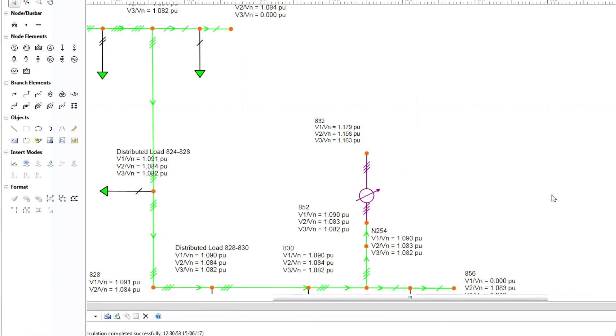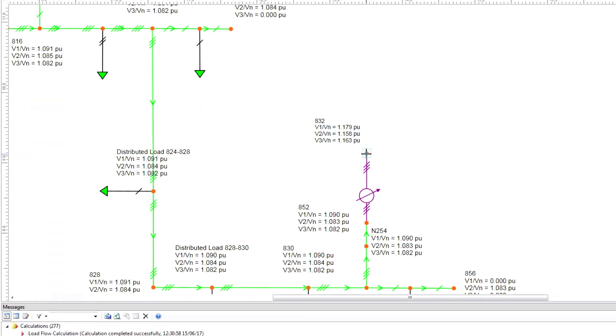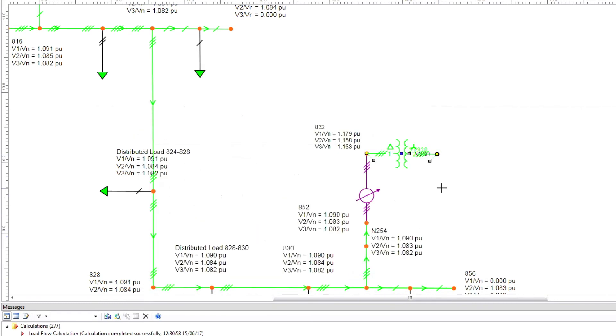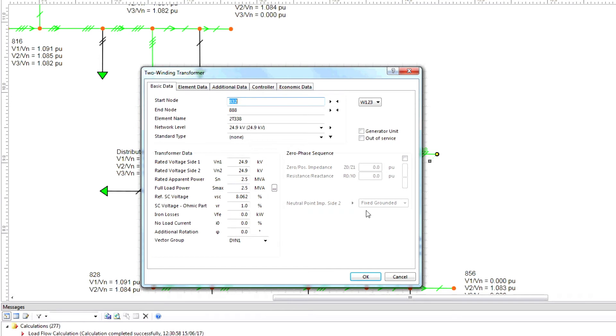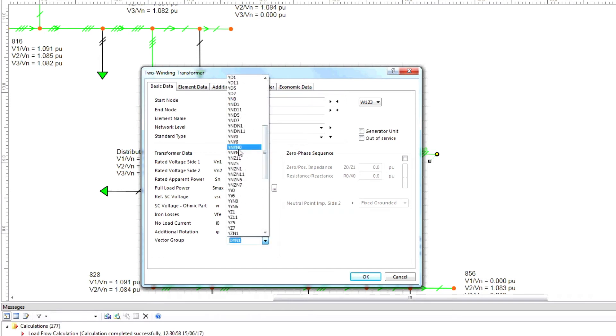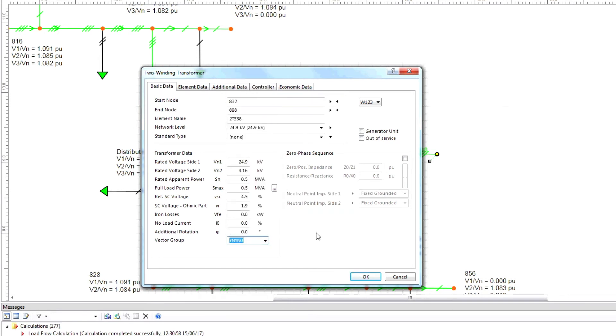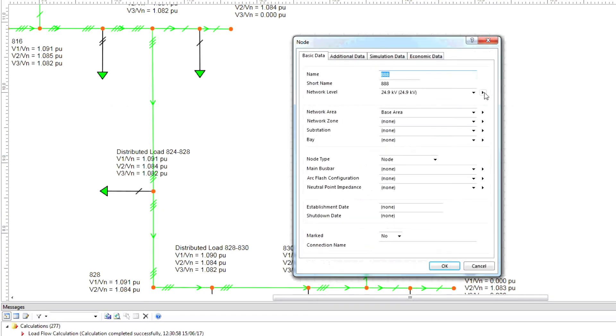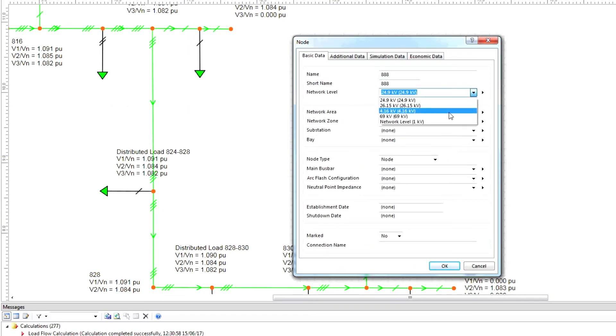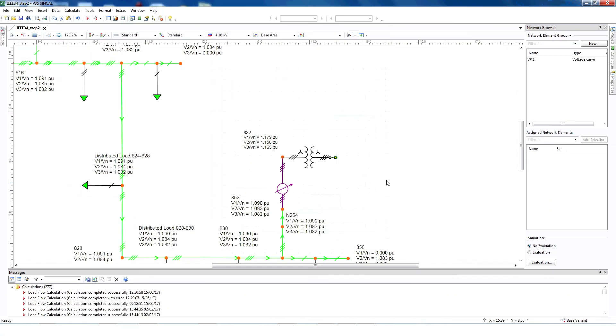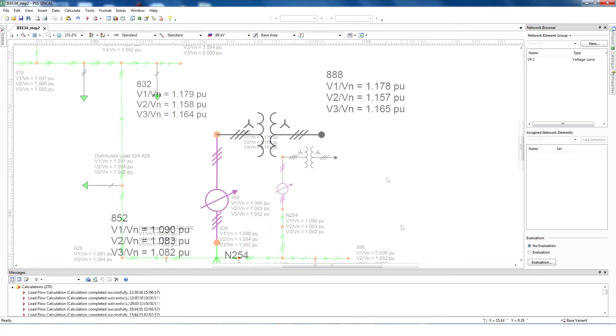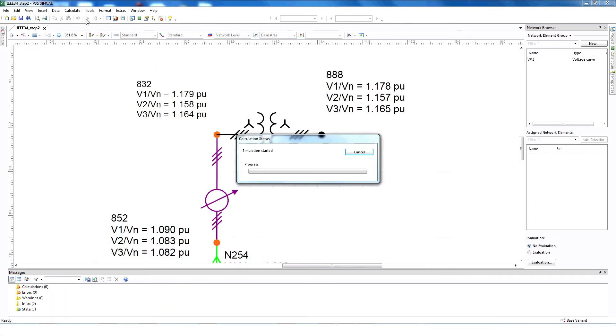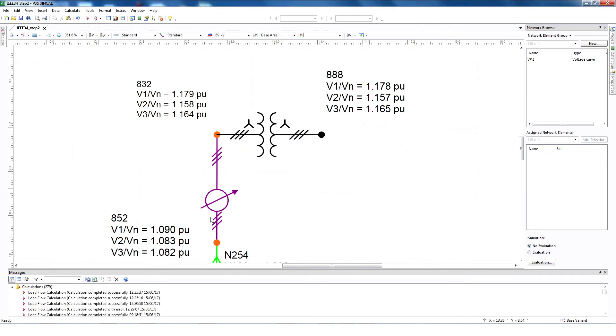To create a transformer model, begin by selecting 2 winding transformer in the toolbox. Then connect node 832 with 888 and click OK. Select the transformer, provide all the necessary information, and click OK. Finally, select node 888, choose the proper voltage level, and click OK. As always, be sure to run the load flow and check the message window to be sure the load flow completed successfully.